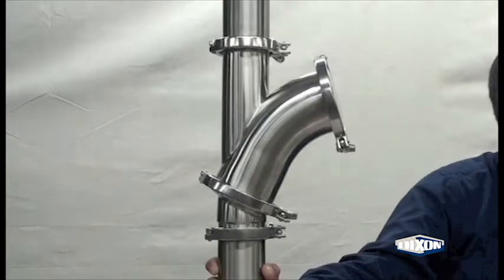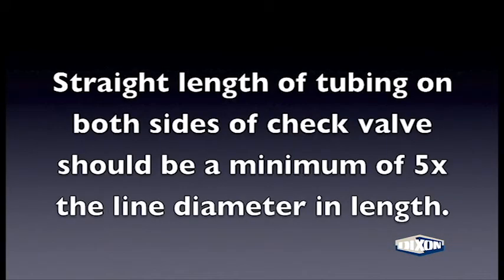The tubing on either side of the valve should be at least five times the line diameter from sources of unstable flow.